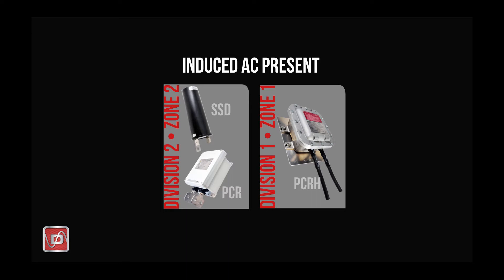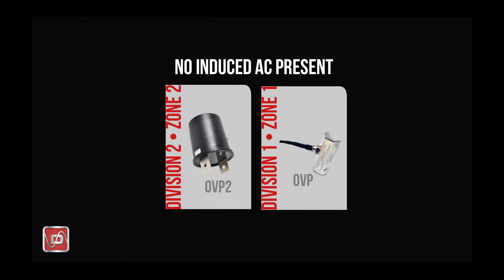If in doubt, assume that induced AC could be present in the future. I urge you to have this selection be your default to assure correct product operation under all conditions. There's no harm in selecting one of these products capable of AC mitigation even if there's no induced AC present, as the product will work correctly for this condition. If you're dealing with an application with no induced AC present, such as an airport jet fuel pipeline, one of the OVP products could be used. The important item to consider is whether or not the site has the potential to have induced AC. If the answer is yes, be sure to plan accordingly, as an incorrect selection could result in the device conducting CP current when you expected it to block CP.